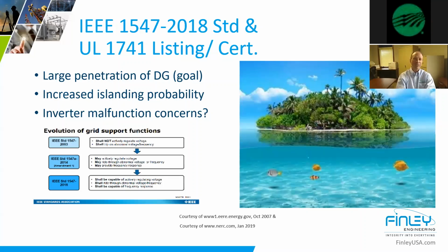You are operating a distribution system and you want these things tripping off because, like we said, you're protecting the public and you want these things coming off the grid to isolate and minimize the fault. But a regional operator does not want big multi-megawatt solar farms coming off grid at the same time. And they have better lobbying ability than you and I do. And that's why the standard's written the way it is. They do not want areas being impacted. So these are being designed to have more fault ride-through capability, what's called, to hang in there, which means you and I have more of a challenge to protect our system from them.